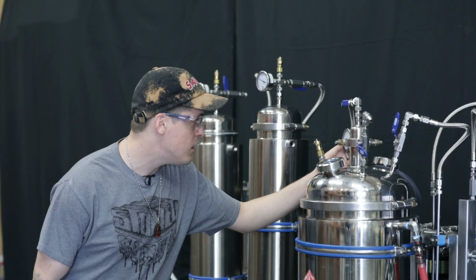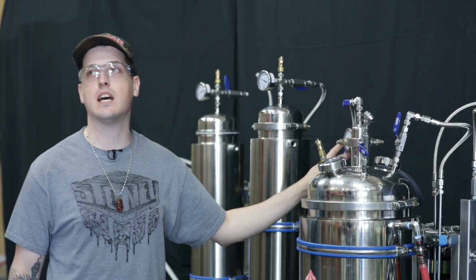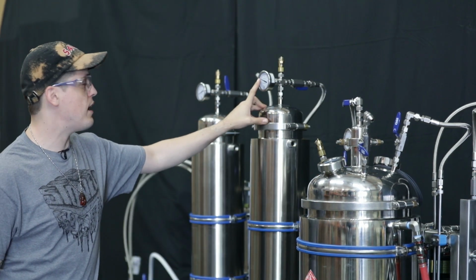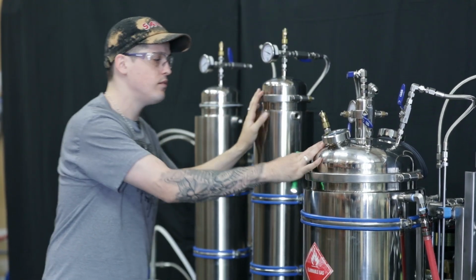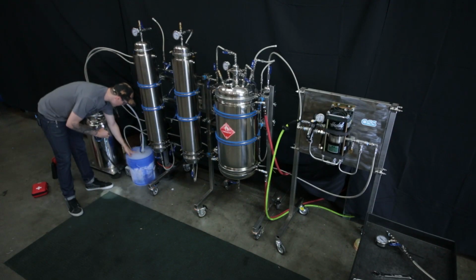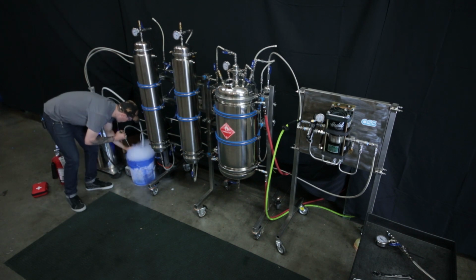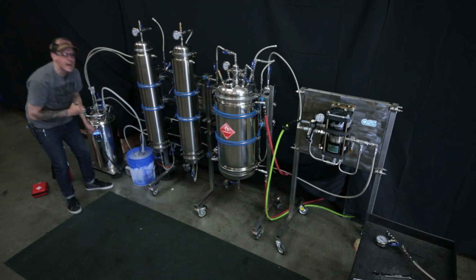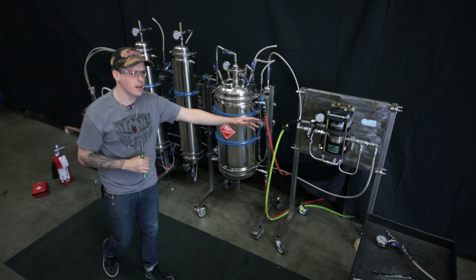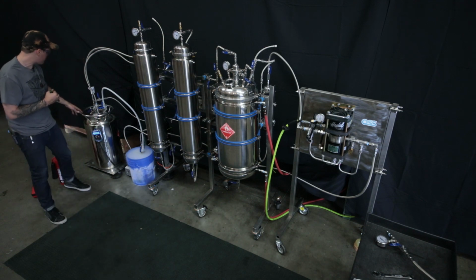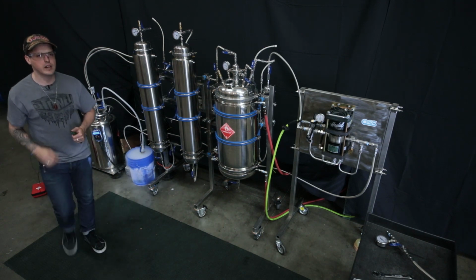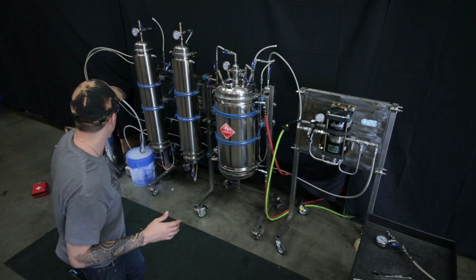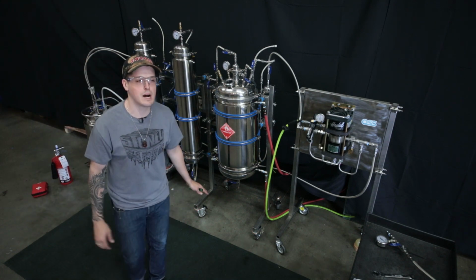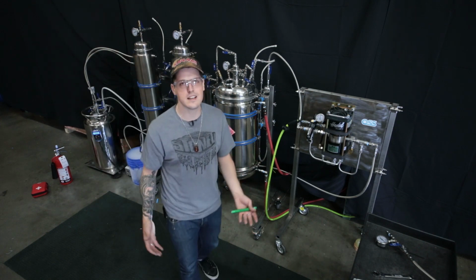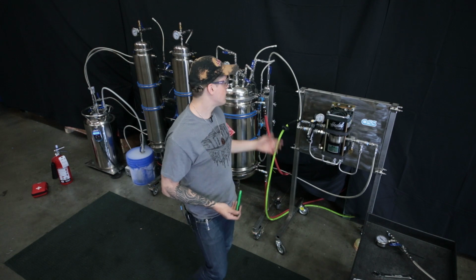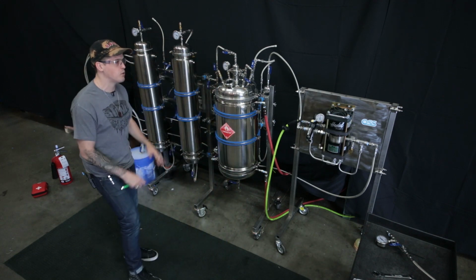So I'm right around 23 or 24 PSI here. I'm right around the same here on my column, so these should be equal. My gauge over here is reading about 28, 27. So there's a little bit of pressure buildup from the start, but by the time it gets to the tank, we're only seeing about 28 PSI. So we're not having a whole lot of pressure in this system. Should be very low pressure operation. That's why when we first started our pressure test, I only did around 60 PSI, because as you can see, we're not even over 30. We didn't even go over half of what we tested.